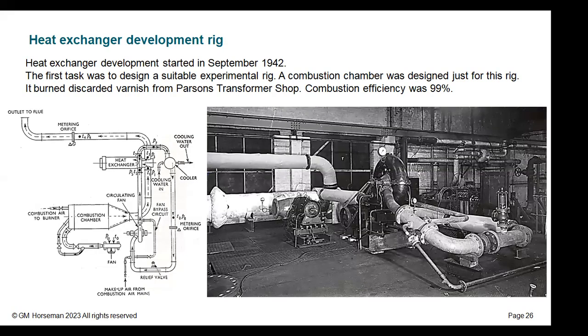This is a view of the rig for the heat exchanger. The diagram on the left is very complicated. I'm just going to simplify it by saying there are two air circuits there. There's one with a combustion chamber, which obviously the gas is going to have the combustion products mixed in it. And that's the one that creates the hot air. And then there's a separate closed circuit with clean air in it, where the heat exchanger transfers the heat from the combustion gas to the clean gas. And that's how it worked.